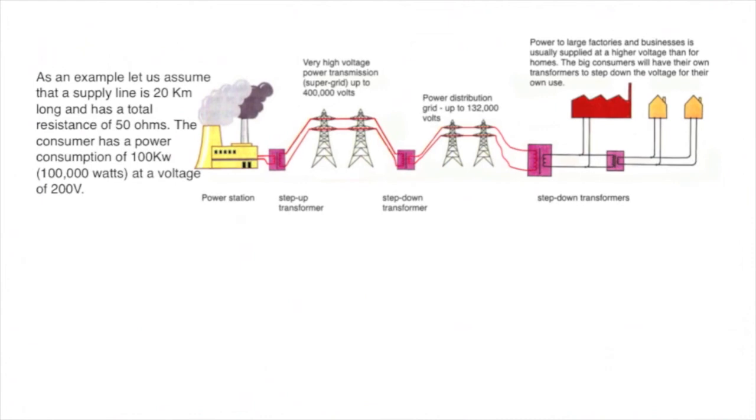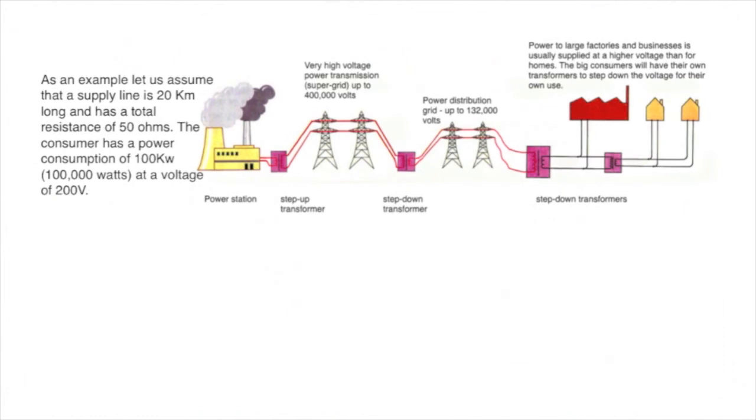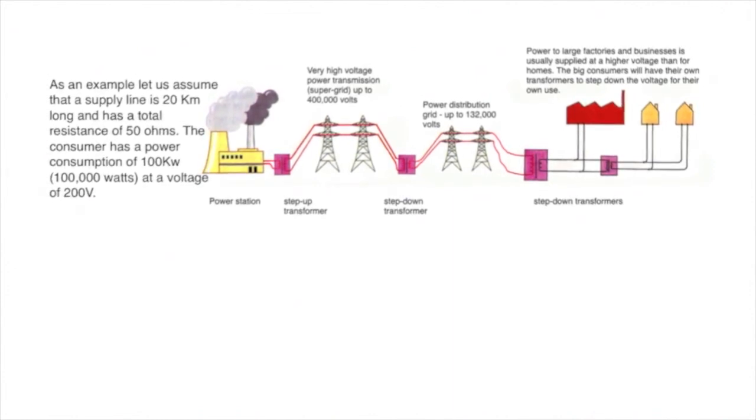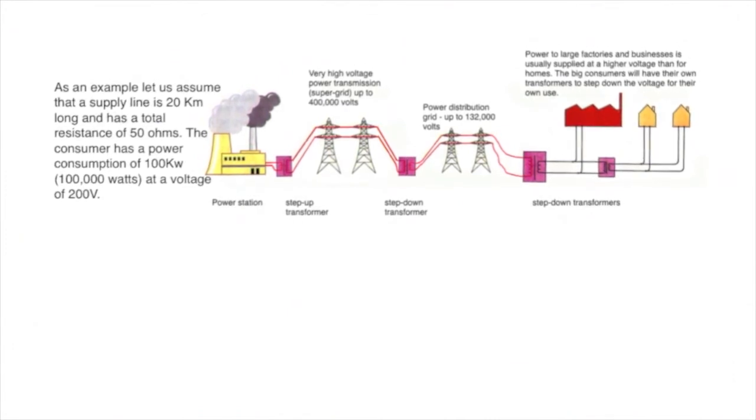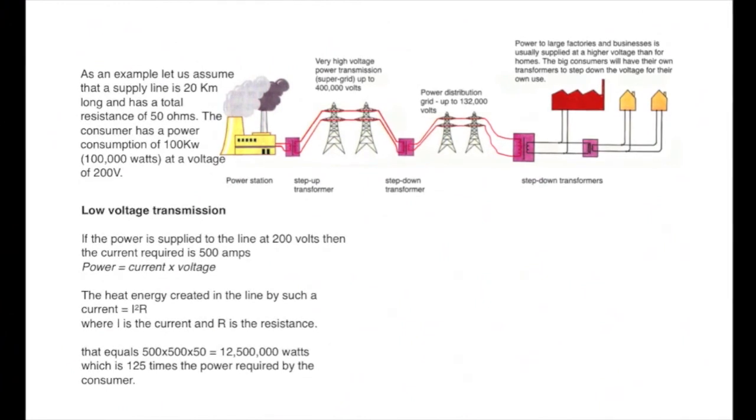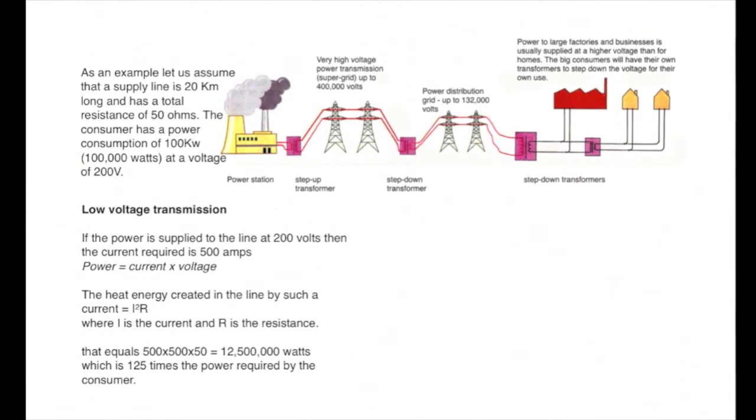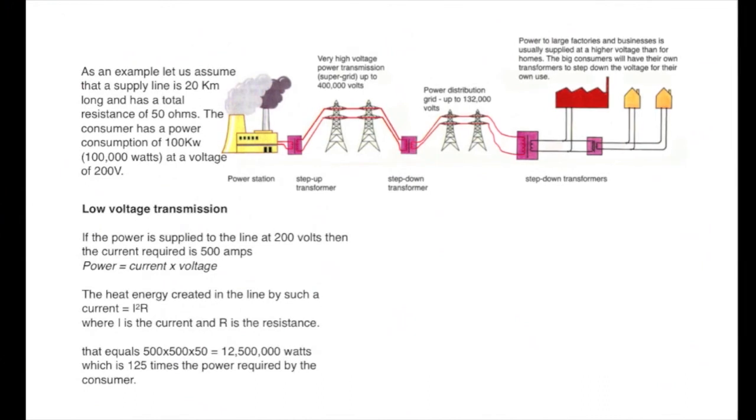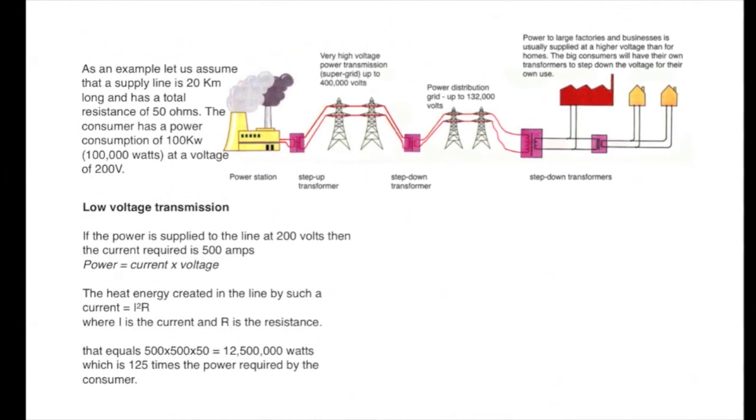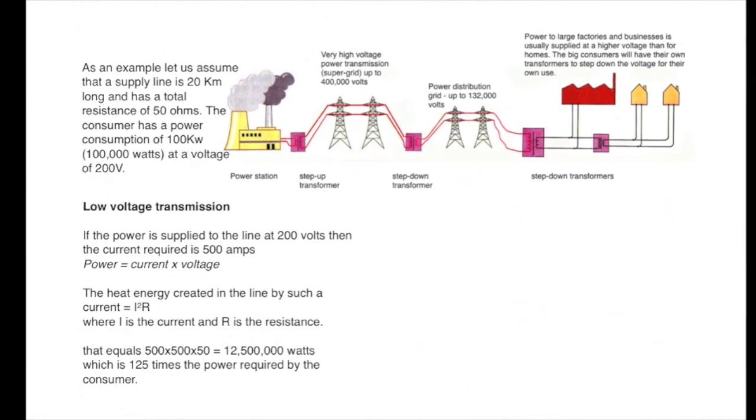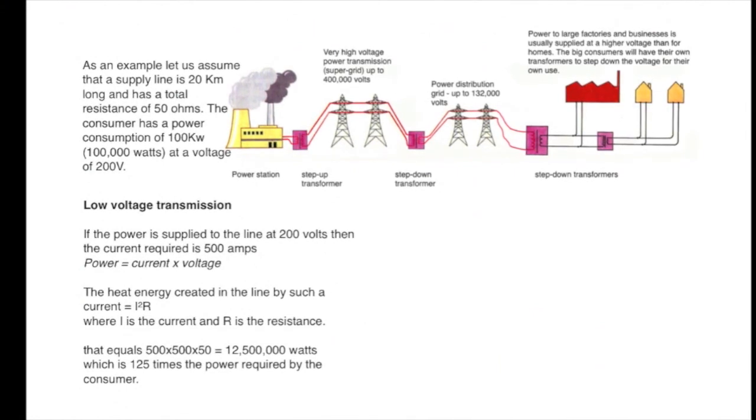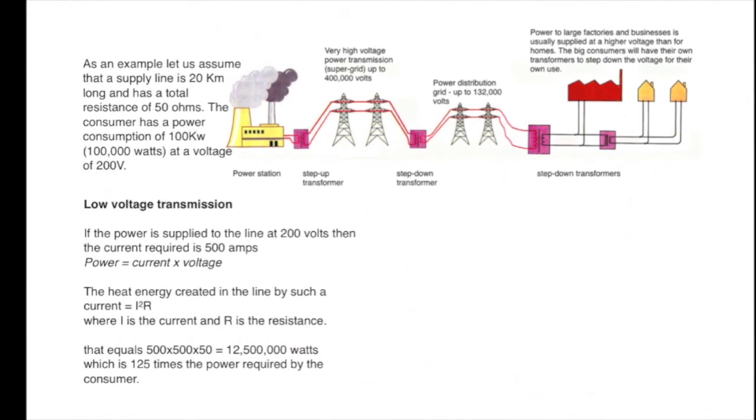To explain why all this has to be done, let's go through a couple of simple calculations. Suppose we have a supply line from a power station, many kilometers long, with a resistance of 50 ohms. The consumer has a power requirement of 100 kilowatts, that's 100,000 watts, at a voltage of 200 volts. If the power is supplied to the line at a voltage of 200 volts, then the current required to be pushed through that power line is 500 amps. That's from the equation power equals current times voltage. Now, when an electric current travels through a conductor, it causes heating due to the resistance, and the heating is equal to I squared R, where I is the current and R is the resistance. I squared R in this case is 500 squared times 50, which is 12,500,000 watts, far in excess of the power that the customer actually requires. A huge amount of energy would be wasted in the transmission. It would not be economical to supply it.